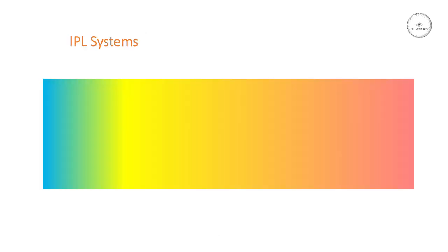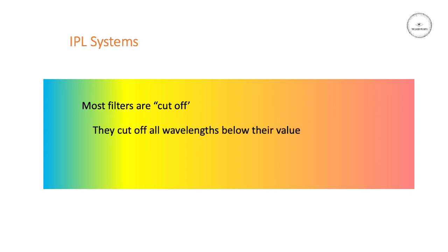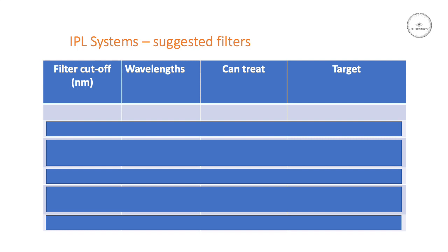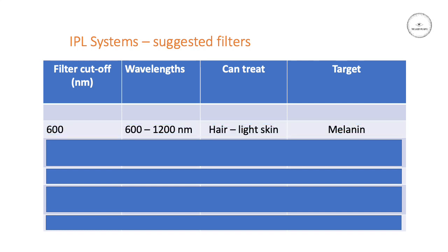In summary, most filters used in IPL systems are cutoff filters. They're designed to cut off all the wavelengths below the value of the filter, and all the wavelengths above that value will get through and onto the skin surface. If you have a filter around about 600 nanometers, then that will let through all the light between 600 and 1200 nanometers, and this is good to target melanin in hair. I suggest you use this for lighter colored skin because the epidermal basal layer should not be too badly damaged by this.